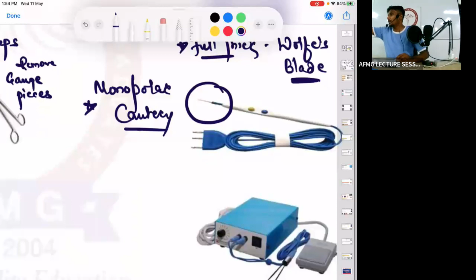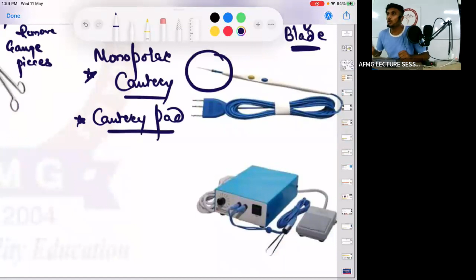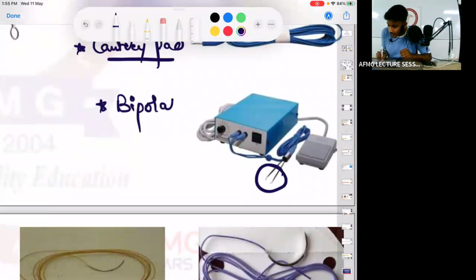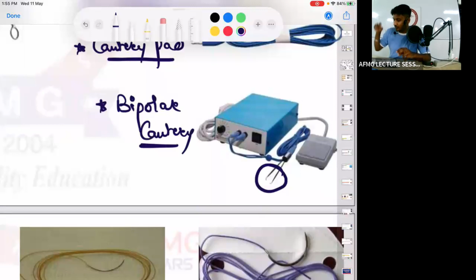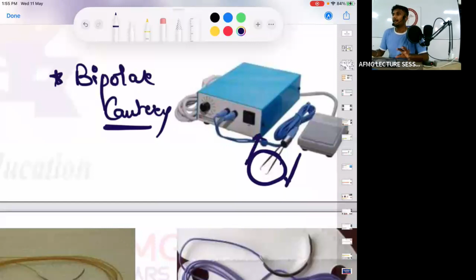So for that we use the cautery pad. Cautery pad is required for which cautery? Monopolar cautery. But cautery pad is not required for which cautery? Bipolar cautery. So here you can see the cautery has how many ends? 2 ends, and therefore it is called bipolar cautery. So if the cautery has prong-like ends, okay, there is a bifid end, it is a bipolar cautery. And a cautery pad is not required because the current will come from one end and go via the other end. Okay, it will not go through the body of the patient.